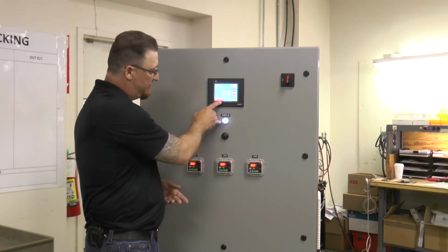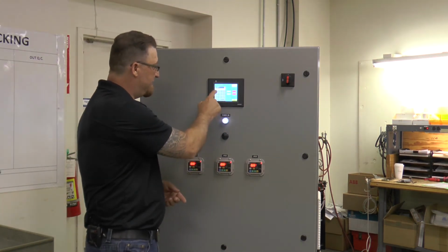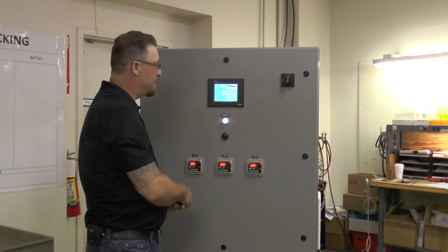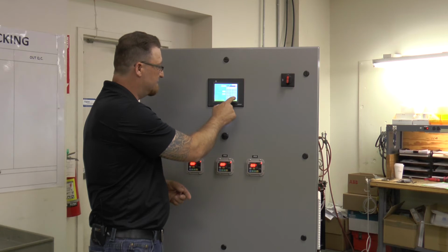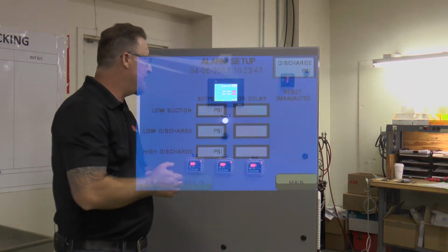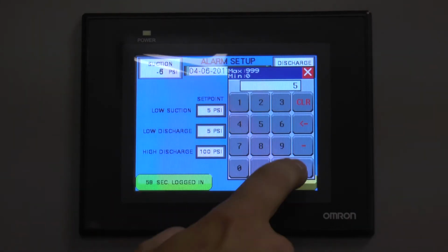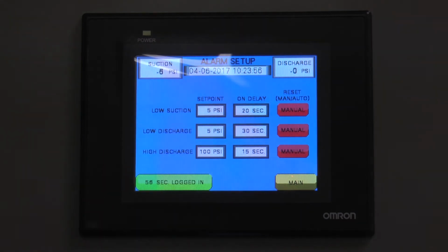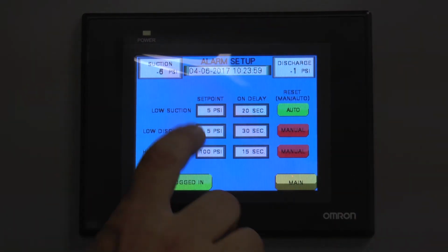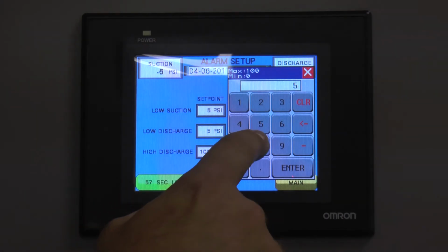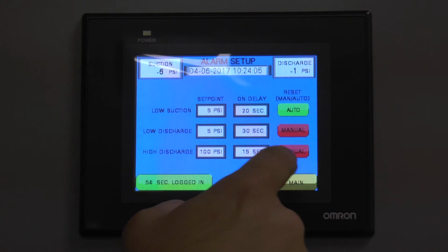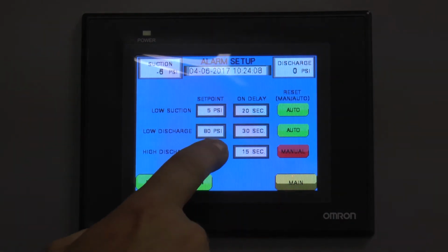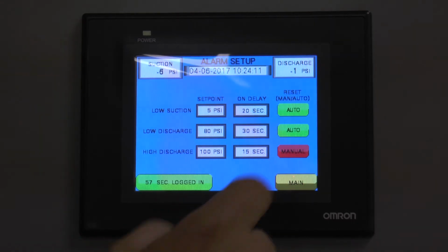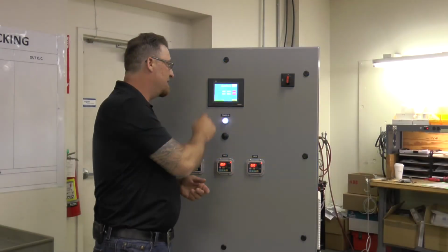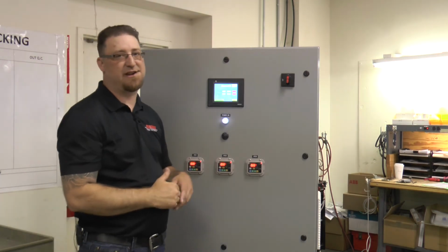So on those, again, you have to push to log in. 1951 is your code. And we can go in and change our set points. Simple. Just press whichever set point it needs to be. And then the on delay for that alarm is for low discharges. So if you have a moment in time where you go below that discharge point, do you want it to automatically trigger? Do you want to wait maybe 5, 10, 15 seconds or even a minute just in case it corrects itself? So that's what the on delays are for. So if we want to wait 15 seconds, which is 4 now, we can do that, or we can change it to 30 seconds. Or if we go back into our configuration screen, we can even change it to minutes.